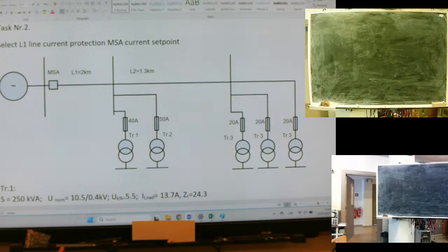depends on the fault location, because it is very simple, the Ohm law. We divide the voltage by the impedance from the source till the fault place. Fault could be very close with a very small impedance, or far away. It means that we will have greater impedance. Greater impedance, lower fault value. I think this is clear. And in this case, the question is, what fault location should we choose?